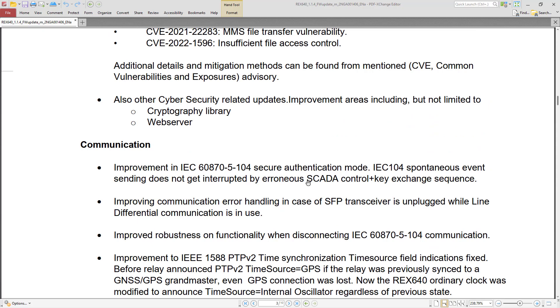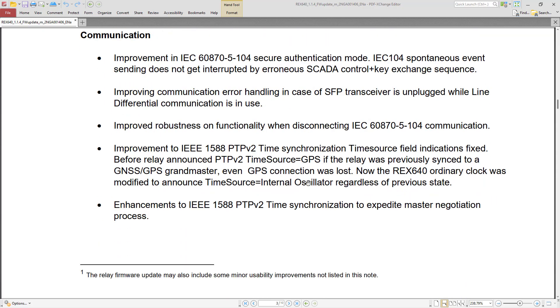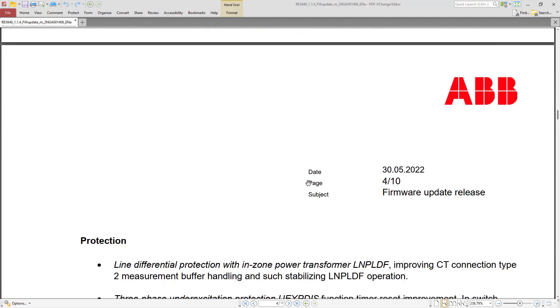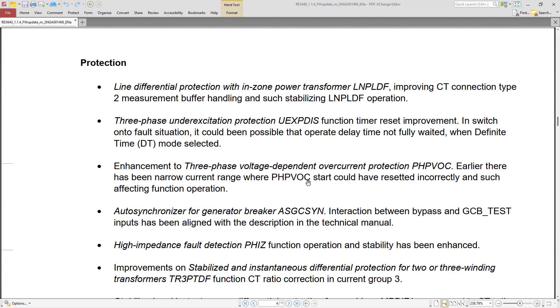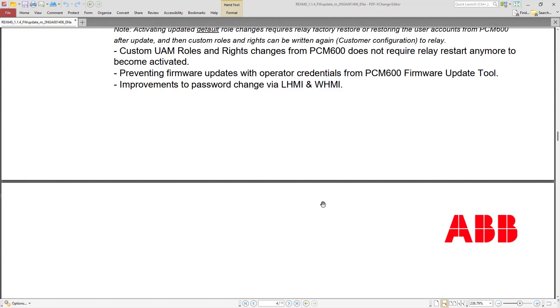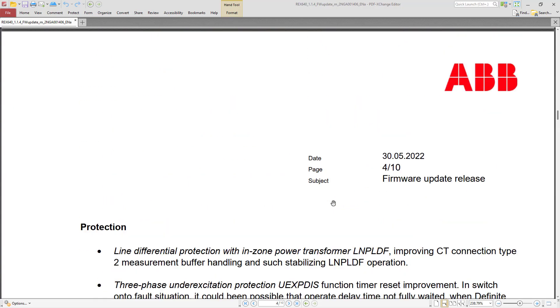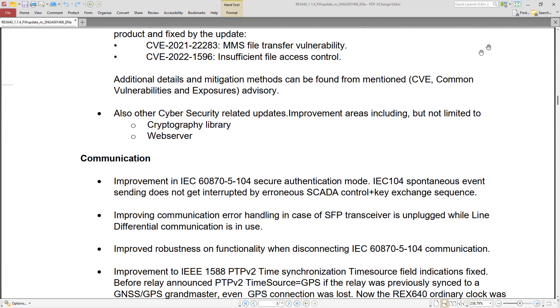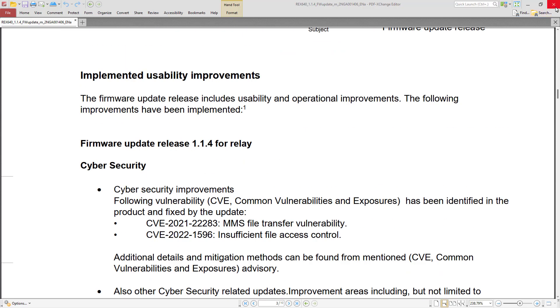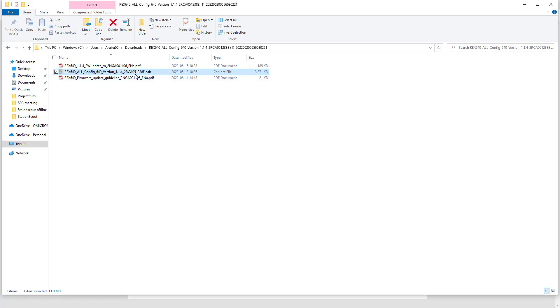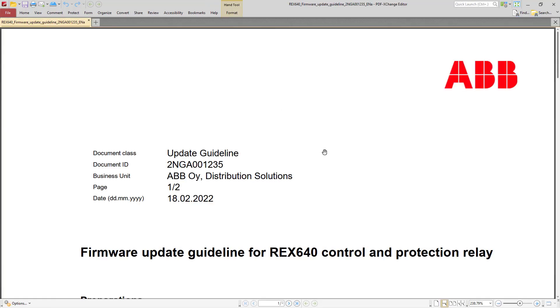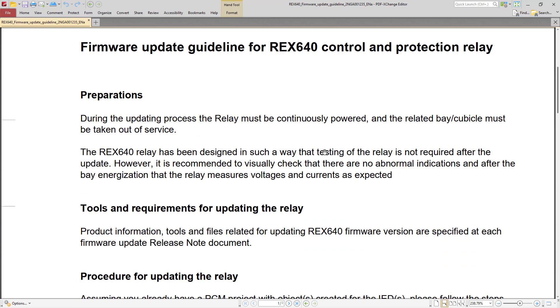It's important to have this update, and it is highly recommended to update the firmware by taking your IED offline. In my case, I'm going to update the IED in my training setup. The firmware file is a .cab file — a cabinet file format — which is used for updating from PCM600. The next file in the package is the manual that will guide you on how to update the firmware.